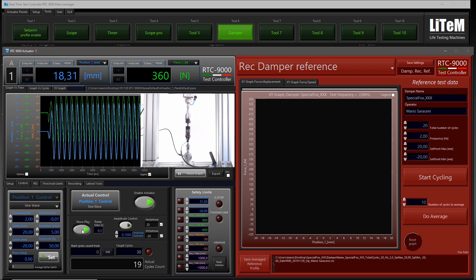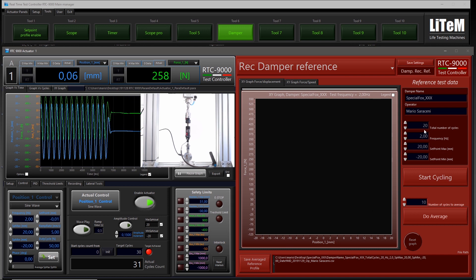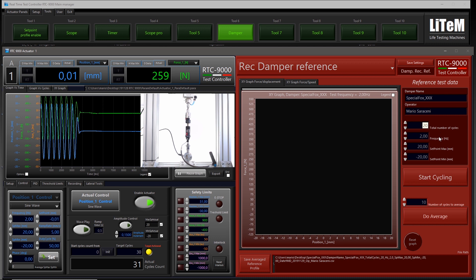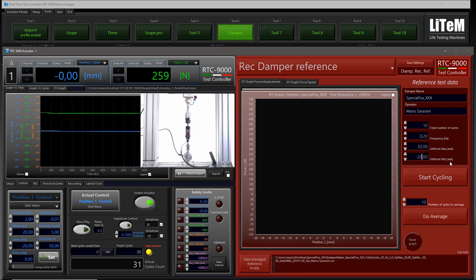This will increase the temperature inside the actuator and should be done before recording the reference. Now I want to do 10 cycles at 0.2 Hz between +20 and −20. This will be the first reference. Here we put today's date; this actuator is a special Fox type, and I enter my name. Let's start cycling.